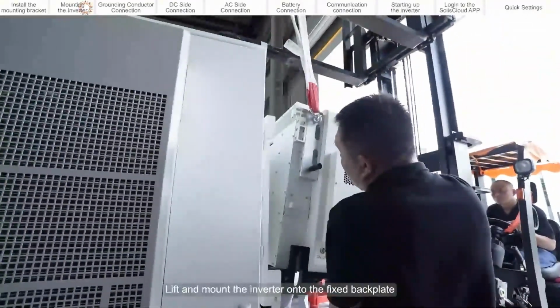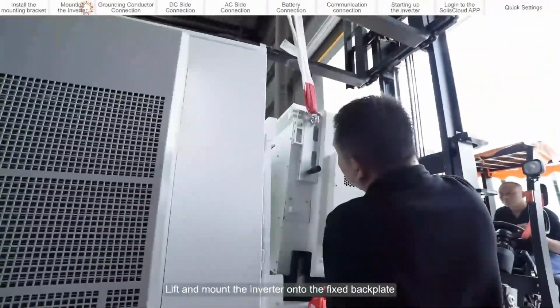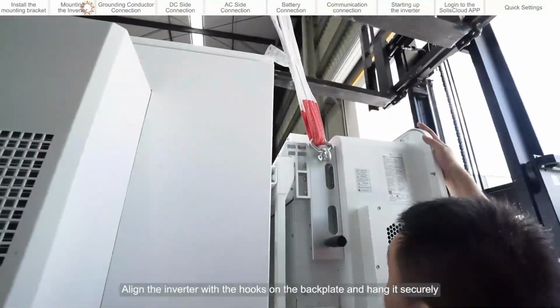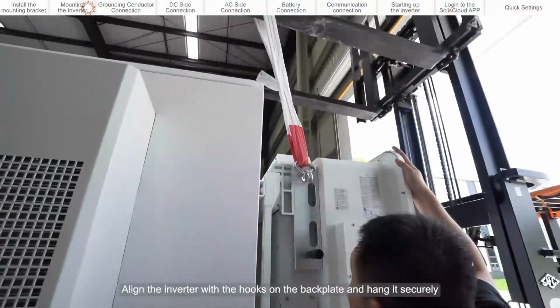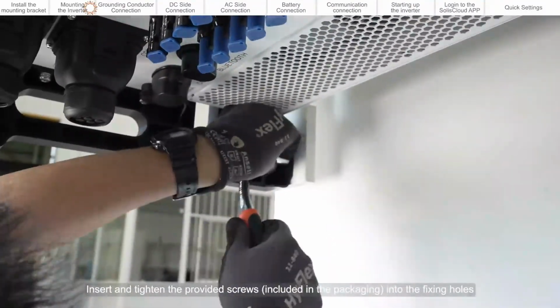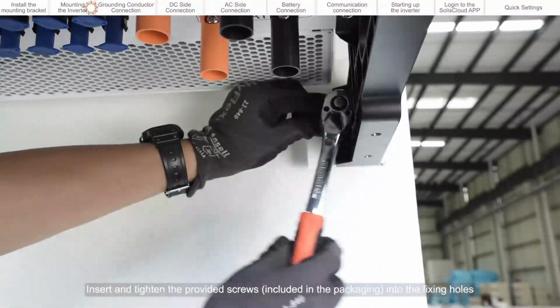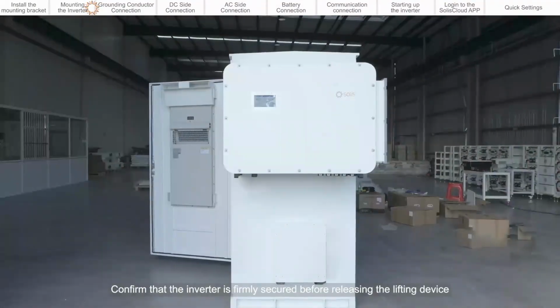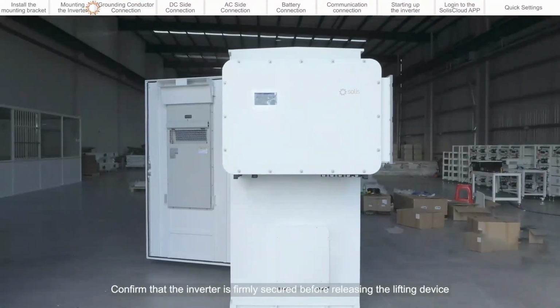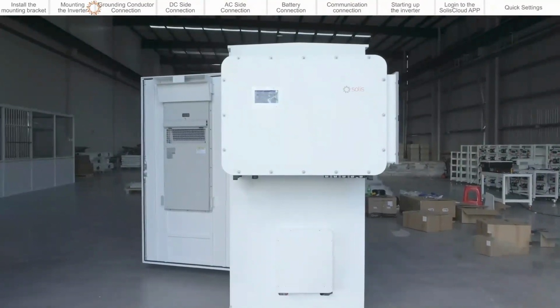Installation positioning. Lift and mount the inverter onto the fixed backplate. Align the inverter with the hooks on the backplate and hang it securely. Insert and tighten the provided screws, included in the packaging, into the fixing holes. Confirm that the inverter is firmly secured before releasing the lifting device.